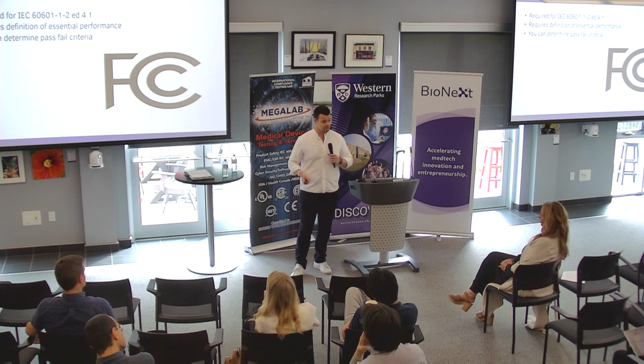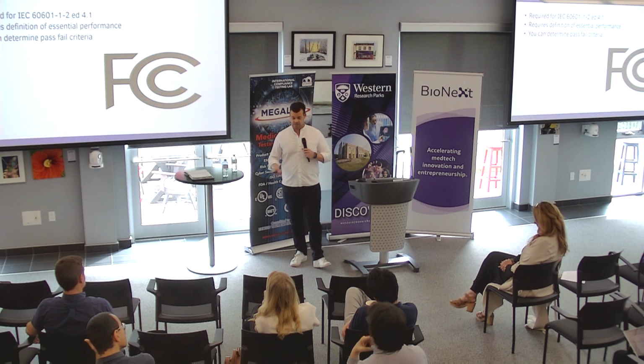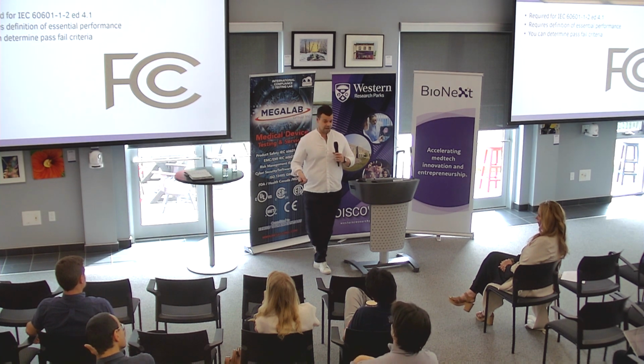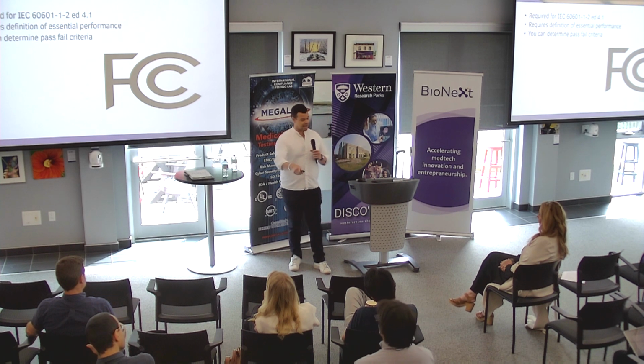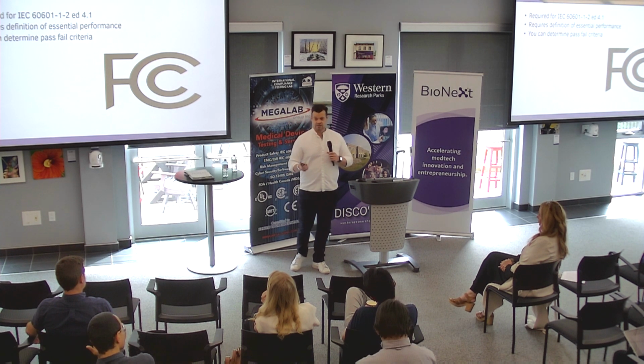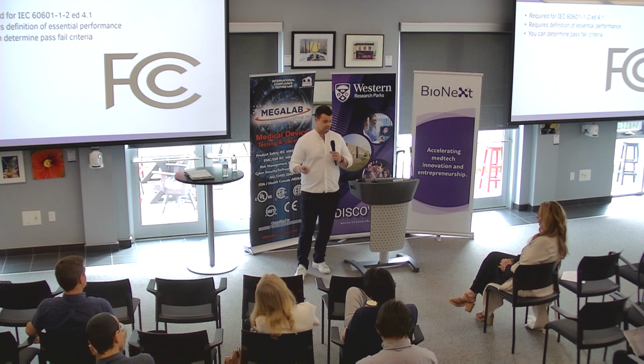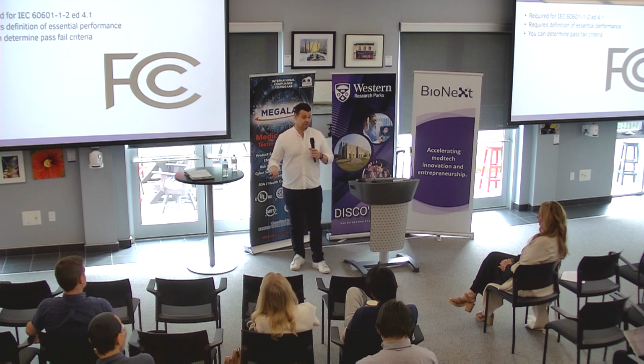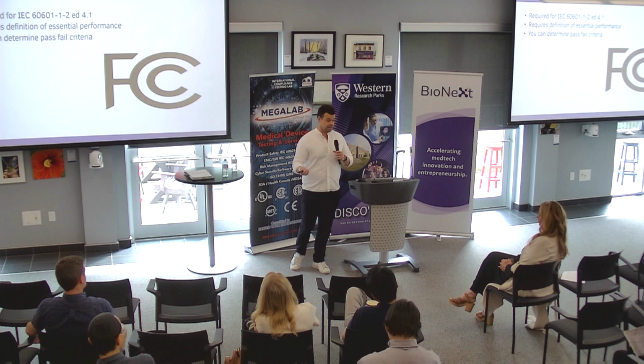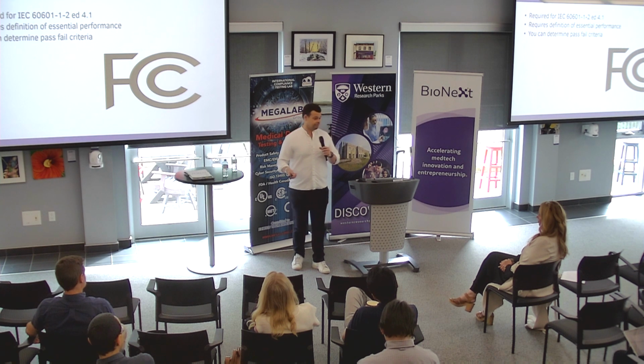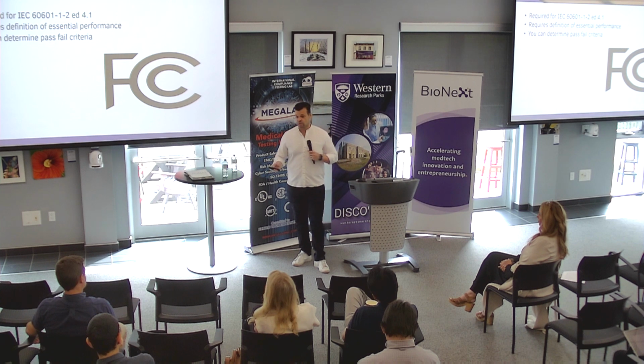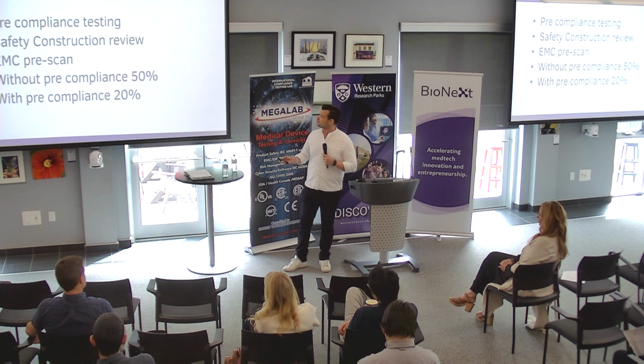So I'll give you an example. You have a hospital bed in an EMC chamber, and we load it with 500 pounds. We put it in and we start zapping the device with radiated immunity. If the little LED readout that says 500 pounds flickers for a second, can you live with that? A lot of people would say, yeah, I can live with that. If it shuts off totally and doesn't show the weight, that's in anyone's mind a fail, right? Because that's a safety hazard. It's not showing how much weight is on there. So something to think about when you're thinking about EMC testing.